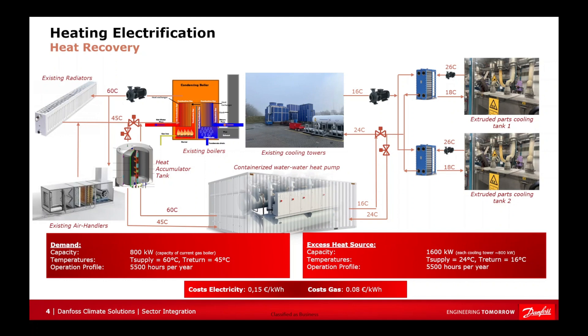The heating demand capacity is 800 kW, which corresponds to the capacity of the current gas boiler and the peak load of the facility heating. The required supply temperature is 60 degrees Celsius, and the return temperature is 45 degrees Celsius. As with the excess heat source, we need to know how many hours per year the facility needs to be heated, which in this case is 5,500 hours.